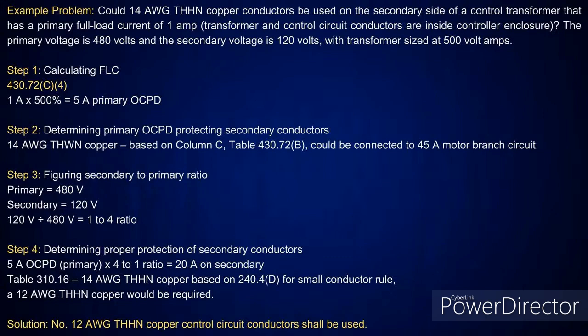Right. And then if I go look at column C in Table 430.72(B), it's going to tell me that for a 45 amp motor branch circuit, it could be connected to what? Number 14 conductors. So I'm going to prove this point now.